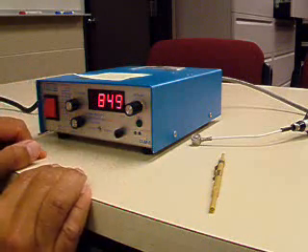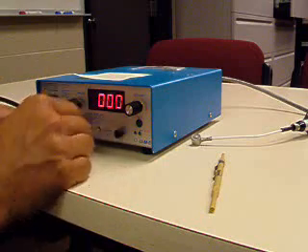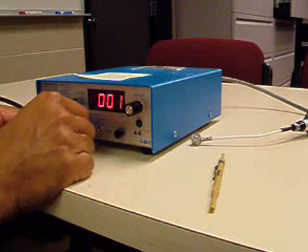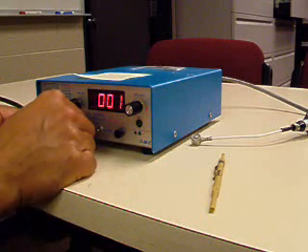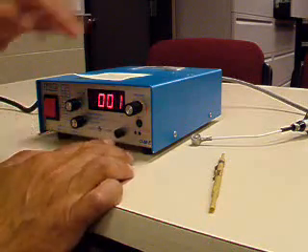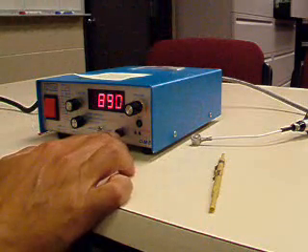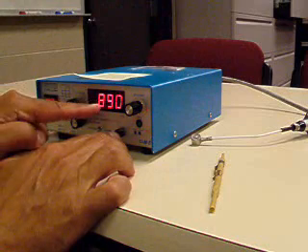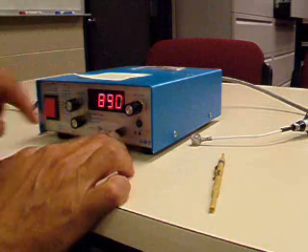I'll switch it into control mode. Notice that I'm going to go back to either the pressure track or the pressure peak, it doesn't really matter which mode. What will happen is when I push this cal button, it'll be like I'm loading this button down in injection molding. When I put it on there, it went above the set point of 850 but the green light did not come on.